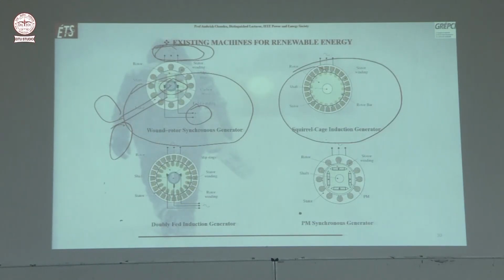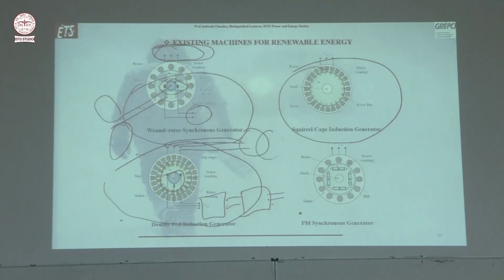Now, the doubly fed induction generator—yesterday we saw it in detail—on the rotor side you have 3 slip rings and 3 brushes, with 2 back-to-back converters, and it is directly connected to the grid, as we discussed yesterday. The advantage here is that these back-to-back converters are only around one-third the capacity of the machine.